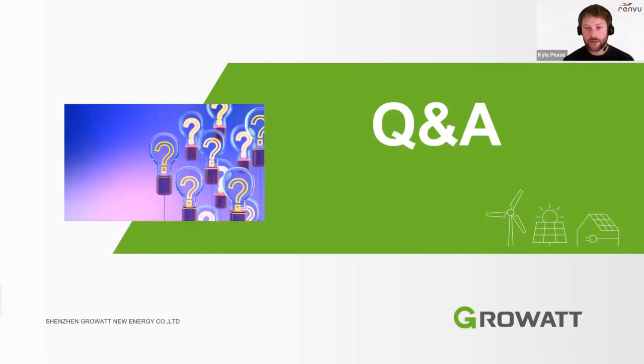All right, and next up we have, can your system handle the startup current surge of a 2-ton HVAC heat pump, surge up to 30 amps? That's a very interesting question. So when you're sizing for the home backup, not only do you need to take into account the fact that it can surge up to 30 amps. So I imagine this is referring to the locked rotor amperage of the HVAC device. So the inverter could handle up to 30 amps.